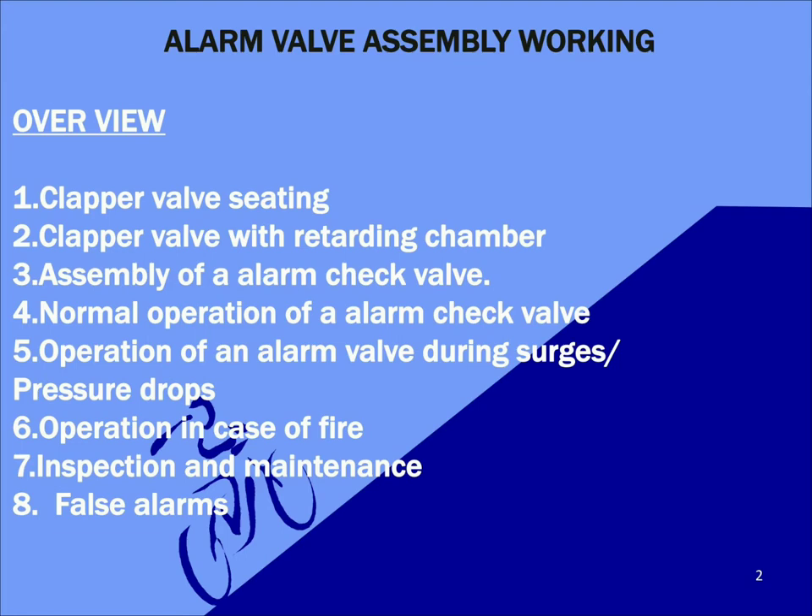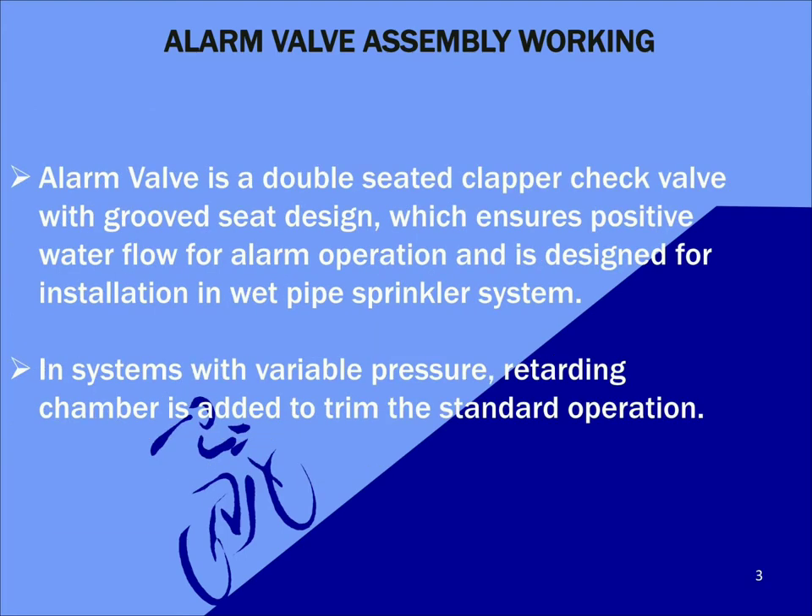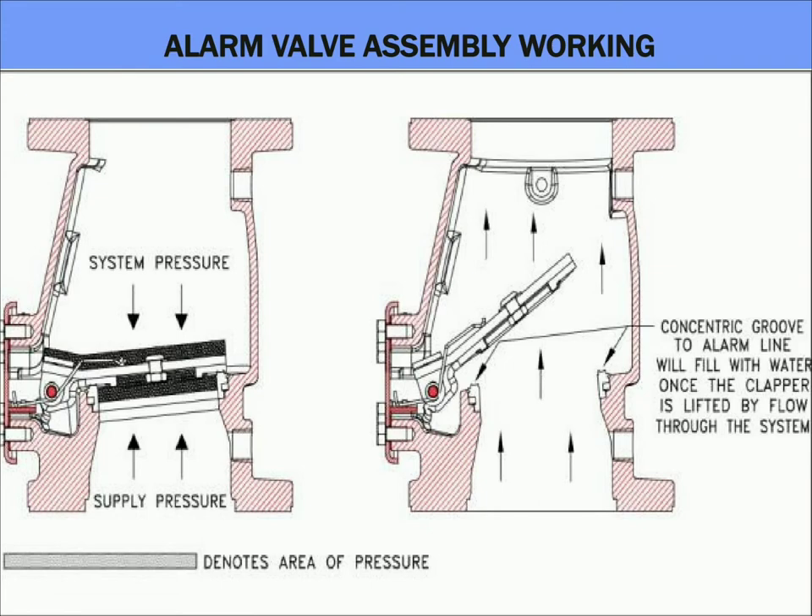Now let's see what an alarm valve is. An alarm valve is a double seated clapper check valve with a grooved seat design which ensures positive water flow for alarm operation, and is designed for installation in a wet pipe sprinkler system. In systems with variable pressure, a retarding chamber is added to trim the standard operation. What you're seeing on the screen is a clapper valve operation without a retarding chamber.